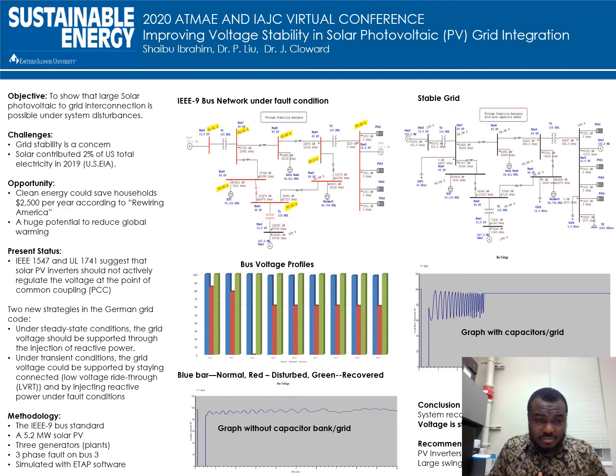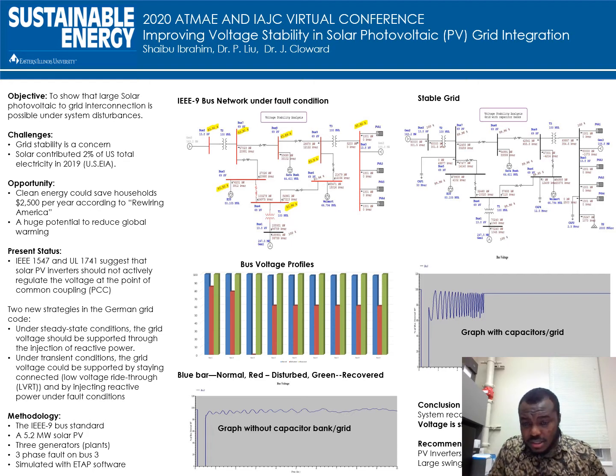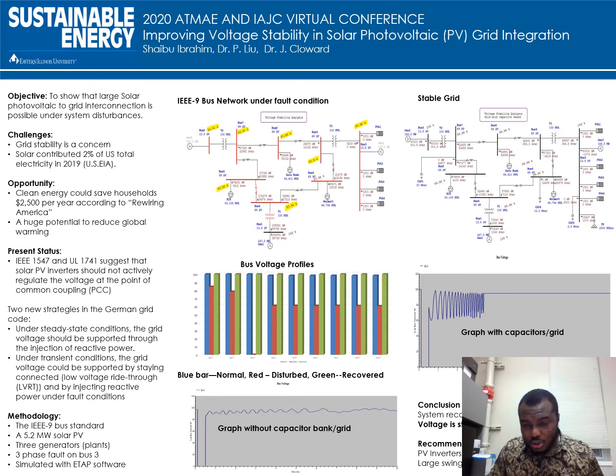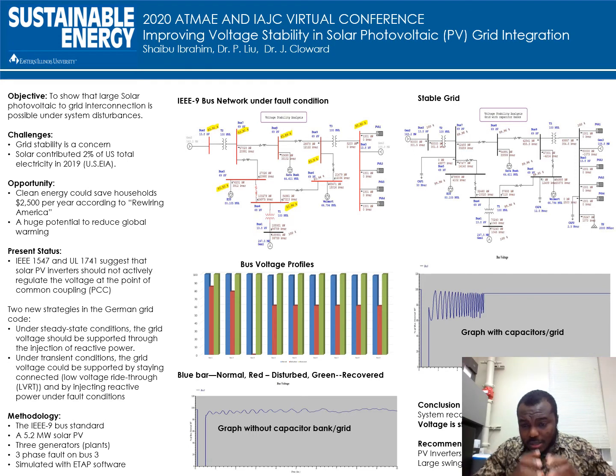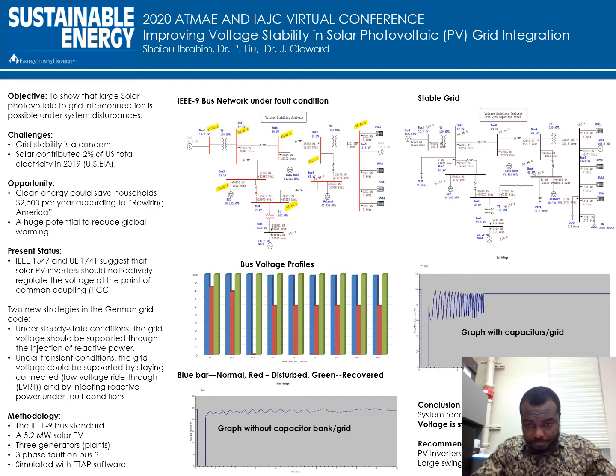The present literature indicates that for solar integration to the grid, IEEE standard 1547 and UL 1741 suggest that solar PVs should not actively regulate the voltage at the point of common coupling. The point of common coupling is where solar is connected to the grid and becomes part of the network. The voltage is supported by devices in the network, and solar is not supposed to take part in supporting the grid voltage. With these constraints, how can we scale up solar power production?